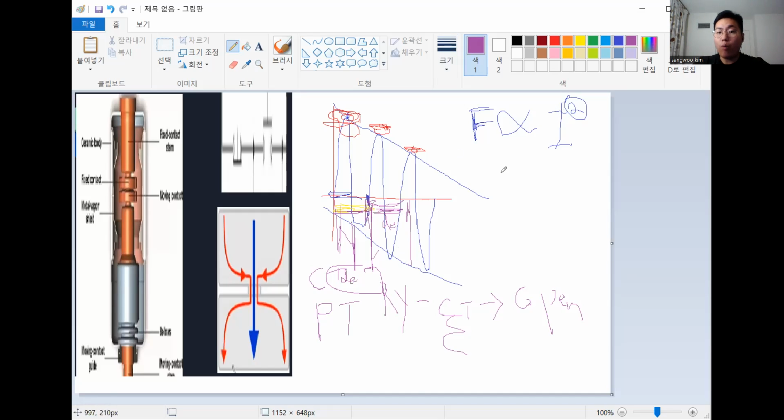But before we open the circuit breaker, it has to withstand at least two peak points. As I said, in a fault current the first cycle's first peak point is the biggest one, the second is a little bit less, the third a little bit less, and eventually it's not a fault current anymore, you know what I mean? So it has to withstand these peak values. So what happened?